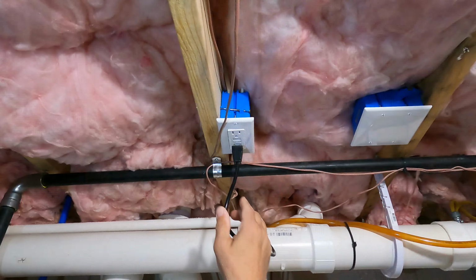Open up the front panel of your FT. All models do open at the front in different ways. Disconnect the igniters and other items that connect to the top of the heat exchanger assembly. All models of the FT will vary in how to take the blower and its manifold off the top of the heat exchanger.